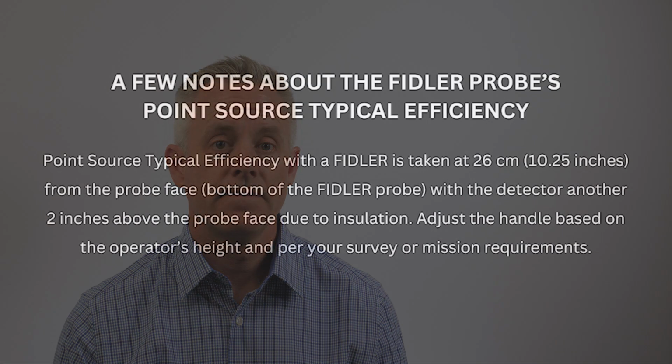Published efficiencies for the FIDLER probe were taken with sources approximately 10.25 inches from the face of the probe.